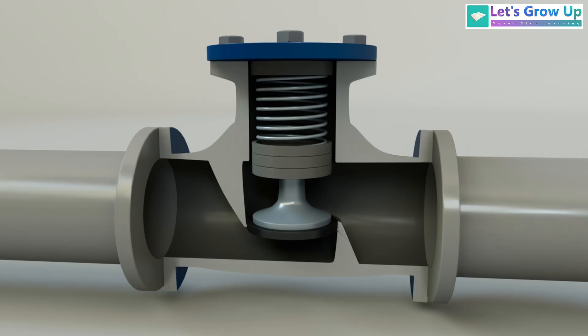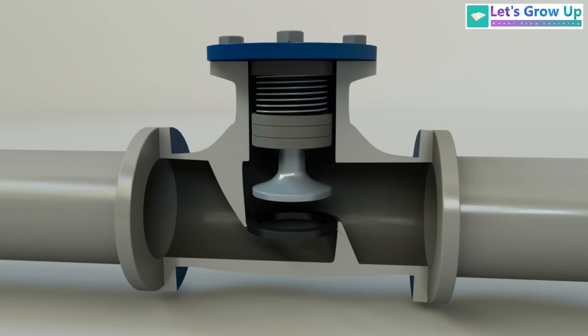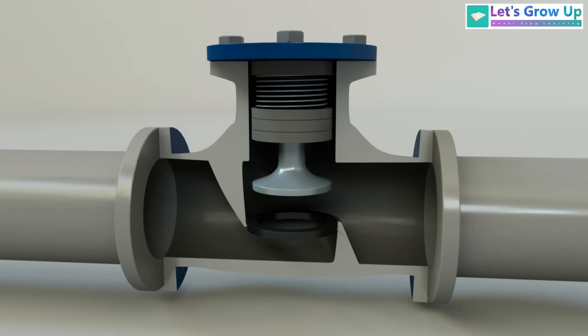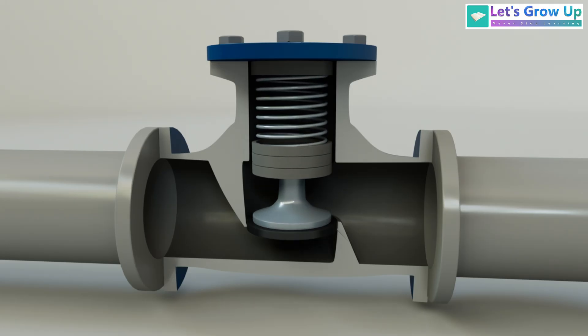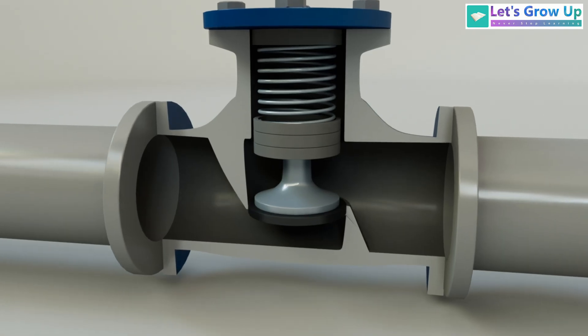When fluid or gas flows in the correct direction, the pressure pushes this piston straight up off its seat. This opens a clear path for the flow. When the flow stops or tries to reverse, the piston's own weight, along with back pressure and sometimes a spring, forces it back down onto its seat. This creates a tight, leak-proof seal, instantly stopping backflow.